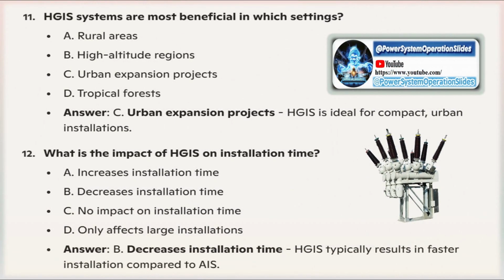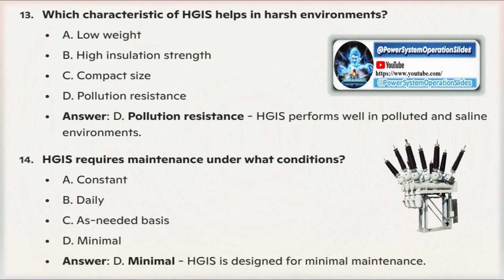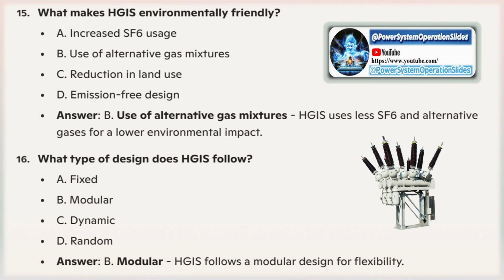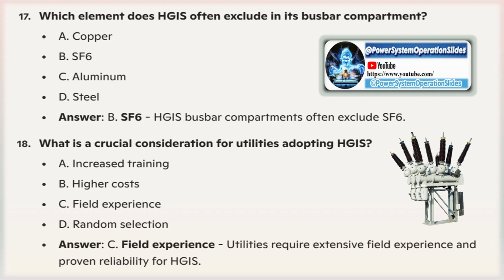Let us discuss the main topic: hybrid gas-insulated switchgear. HGIS offers significant environmental benefits by reducing SF6 gas consumption compared to traditional SF6 gas-insulated switchgear at the same voltage level. Here's a more detailed look at these benefits. Reduced SF6 gas consumption: HGIS can save up to 2/3 of SF6 gas consumption compared to conventional GIS. This reduction is achieved by combining gas-insulated components with solid insulated busbars, which eliminates the need for SF6 in certain parts of the switchgear.